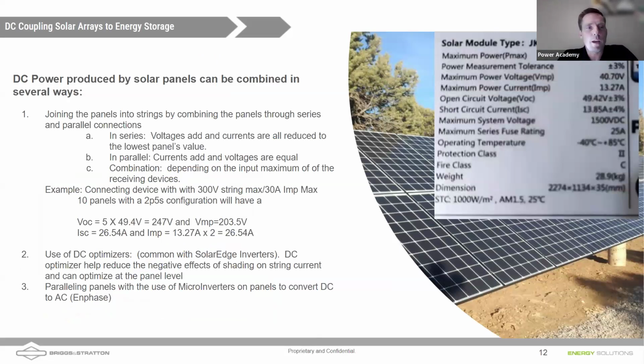Let's talk real quickly about combining solar panels to form arrays. Each individual module has the characteristics we gave before. I am showing you a picture of a real solar panel's label in the top right there. If we combine solar modules together in series, then the voltages add up and increase. If we combine solar modules in parallel, meaning we connect the positive sides of both panels together and the negative sides of both panels together, our currents would increase. It would be the addition of those two currents, but the voltages would be equal. Typically, solar arrays are connected either in a string of single panels, or maybe a couple of panels in parallel and pairs in a string that's in series.